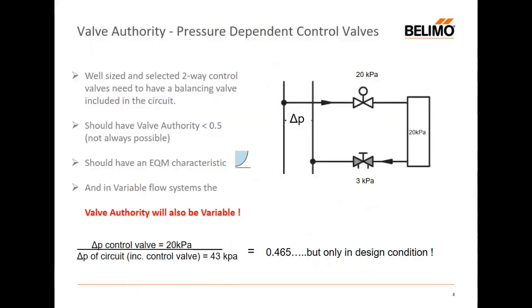So first off, we look at valve authority and we say, let's look at an example. We've got a very simple circuit here with a 20 kPa cooling coil. We've selected a 20 kPa control valve. We see a balancing valve, which is giving us 3 kPa.